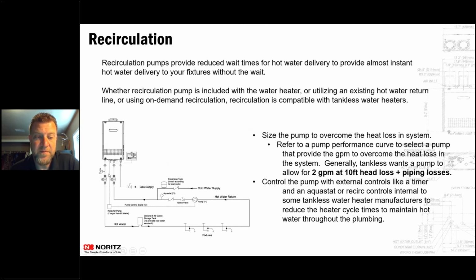So if you are adding that recirc pump, just make sure that you have enough gallons per minute, that you add an expansion tank, and that you have it controlled either with a timer or an aquastat. A lot of manufacturers will void the warranty on the units if you aren't controlling that recirc with a timer and aquastat. With our unit, if you use our pump, it's connected to the unit itself, so the unit controls the pump, and you do not have to add an aquastat or a timer, because that timer and aquastat is actually built into the unit itself.